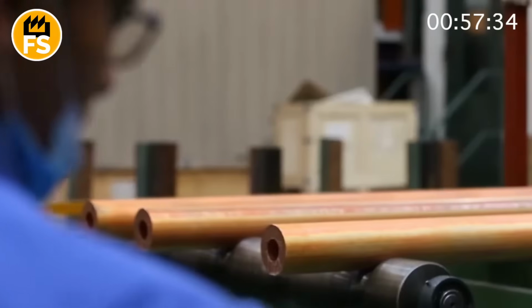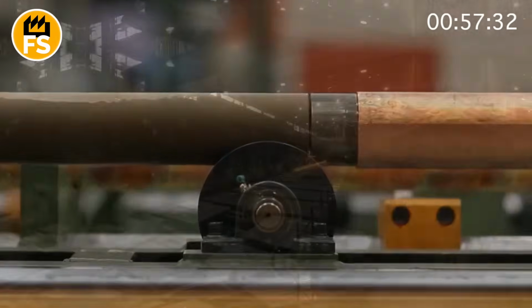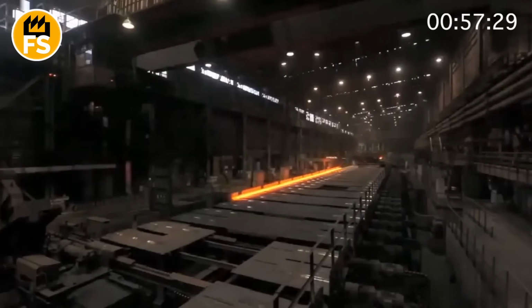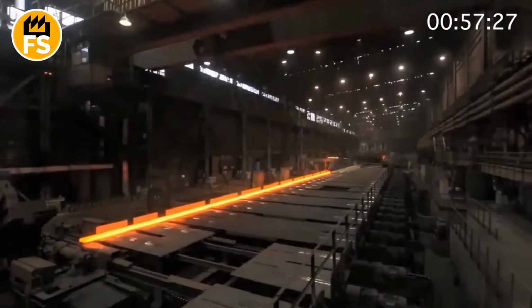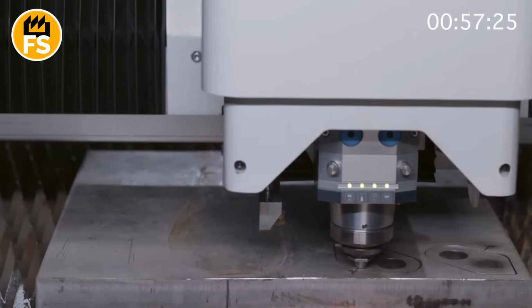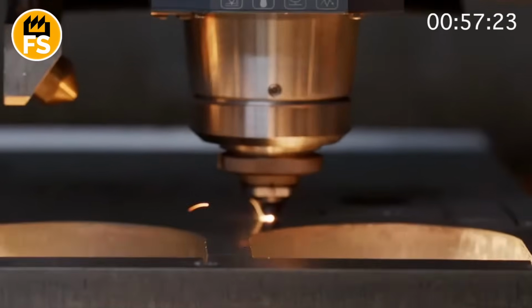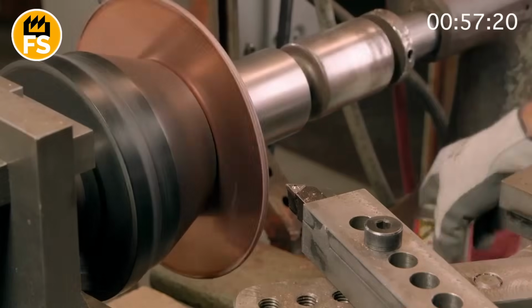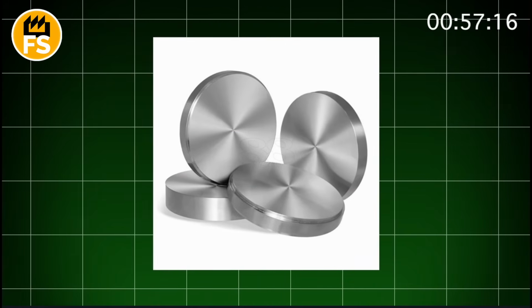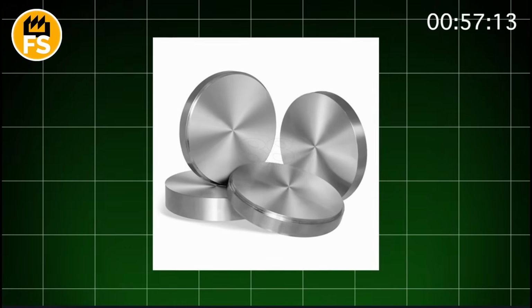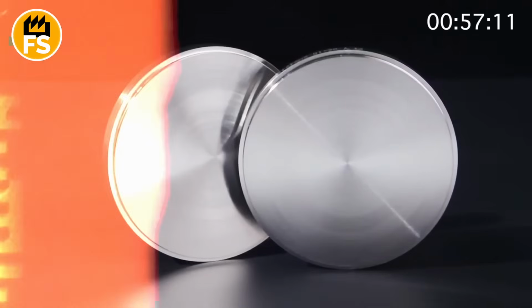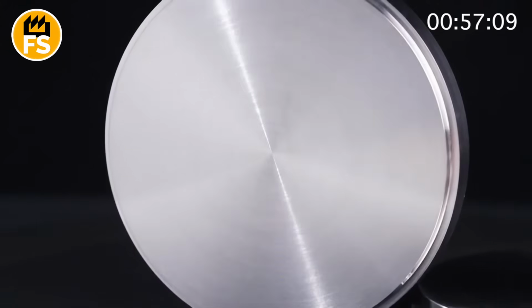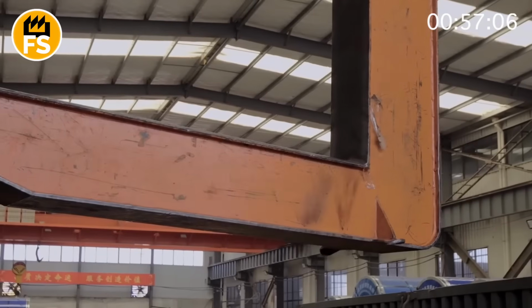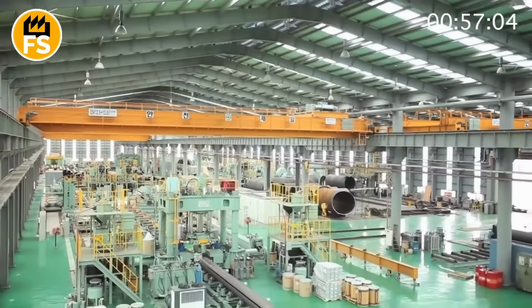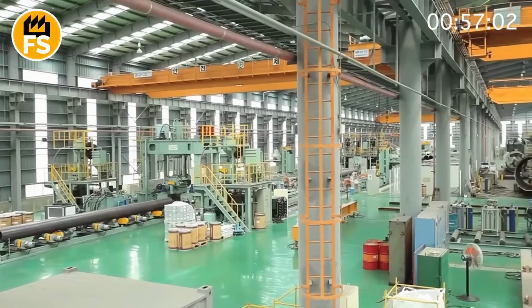To start manufacturing, we need to prepare the materials. Copper tubes are made from high-quality copper, often with internal spirals or microfin structures to improve turbulence and heat transfer. Before further processing, the tubes undergo cleaning and annealing to relieve internal stress. Aluminum fins are cut from aluminum alloys, such as 8006 or 1199, which have excellent thermal conductivity and corrosion resistance. The fins can have various shapes: straight, wavy, perforated, to optimize airflow and heat transfer.